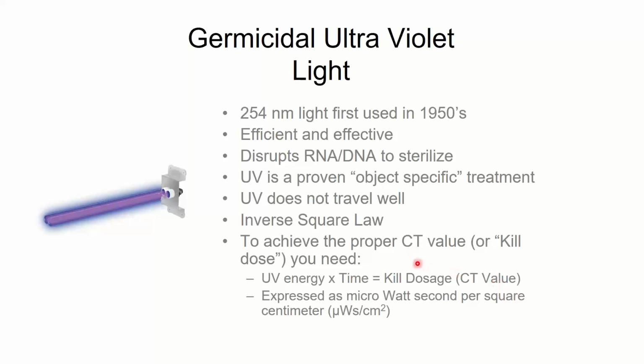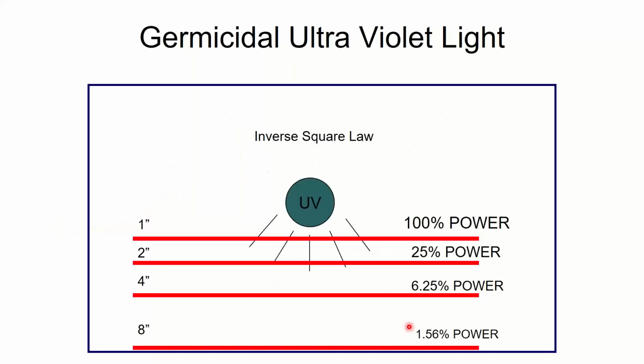But in order to kill it, I need a certain dosage, a certain CT value, and that's a function of the UV intensity of the light source and the time of exposure. And there's an actual measurement for that, microwatt seconds per square centimeter. This big long unit of measure over here. Right? So UV energy and time duration is what's going to get my kill dosage. My energy is a function of how close I am to the light and how bright the light is to begin with. So just like with the sunshine, if you're on the top of a mountain, you're going to get more sunlight shining on you than if you're in a valley, right? You're closer to the sun. You will burn slightly faster.